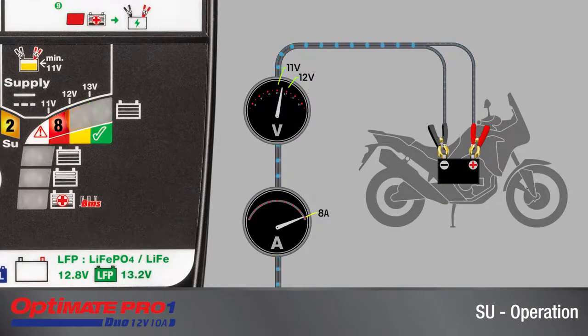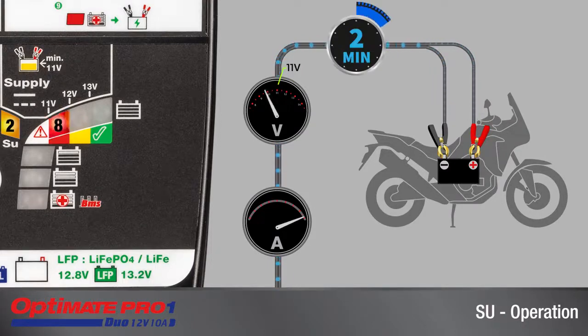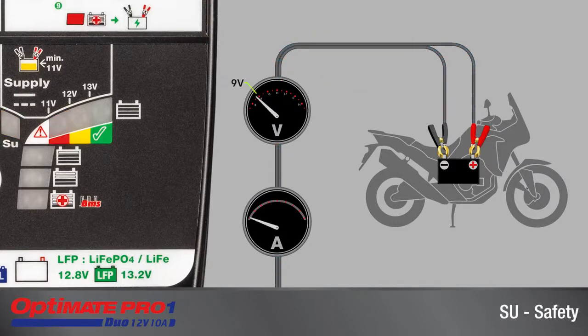LED 8 is lit when the voltage is between 11 and 12 volts. Current draw is at maximum. LED 8 blinking indicates that the battery voltage is below 11 volts. The supply mode will be interrupted if the voltage has not risen above 11 volts within 2 minutes. The supply mode will shut off if the voltage has dropped below 9 volts.